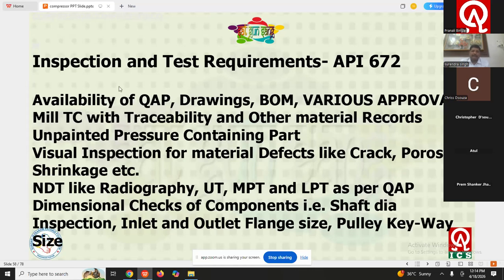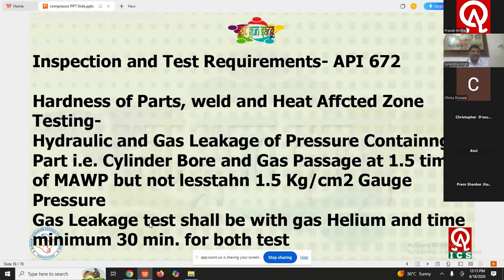The same check parameters are applicable to the API 672. Availability of the QAP, drawings, BOM, various approvals, then the NDT methods. Same visual inspection you have to do for the defects, crack, porosity, dimensional checks for components, shaft dia inspection, then inlet and the outlet flange, pulley keyway, etc. Same hardness you have to check at parent metal, weld, heat affected zone, then testing.